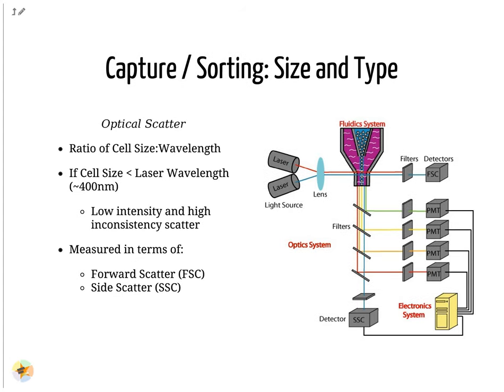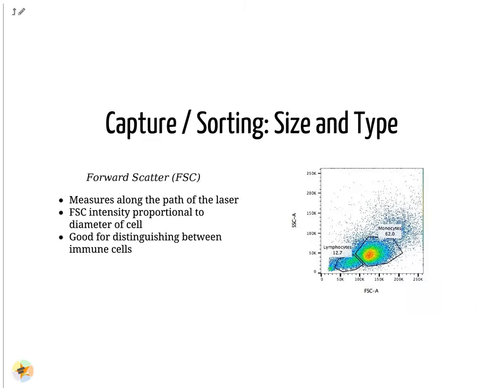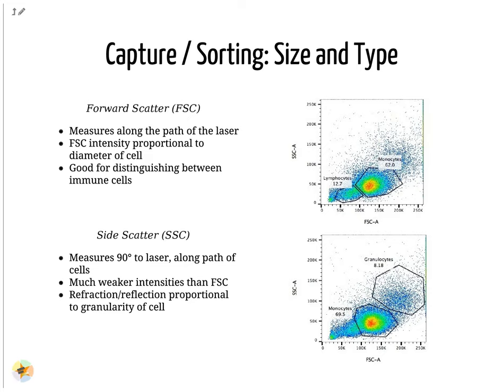Optical scatter properties can be used to probe size and consistency of the cell, where cells with a smaller size than the laser wavelength yield lower intensities and more inconsistent scatter patterns. There are two main types of optical scatters: forward scatters and side scatters. Forward scatter is aligned with the main laser and measures the diameter of the cell, ideal for distinguishing different cells by their size profiles, for example monocytes, which are typically larger than lymphocytes. Side scatter is perpendicular to the main laser and measures the granularity of the cell, ideal for distinguishing cells with less defined internal structures, such as granulocytes.